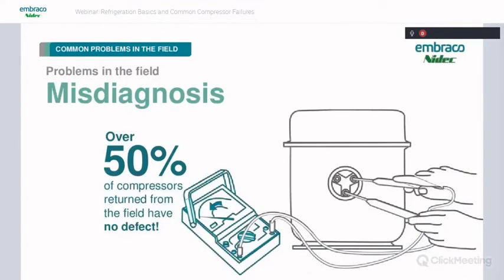So another problem in the field is misdiagnosis. And Embraco tells us that over 50% of the compressors returned from the field actually have no defect. When they do a run of checking warranty compressors from the field, this is what they're finding. They throw them on the machine, and the compressor starts and runs and is working perfectly. This just means that better diagnosis should be done, for a couple different reasons. We don't want to change a compressor that we don't have to, for the extra work of it, and we also don't want to charge a customer to change a compressor that may not need to be changed.